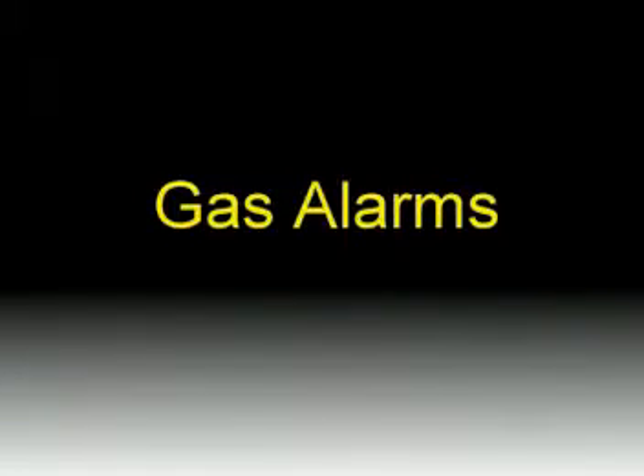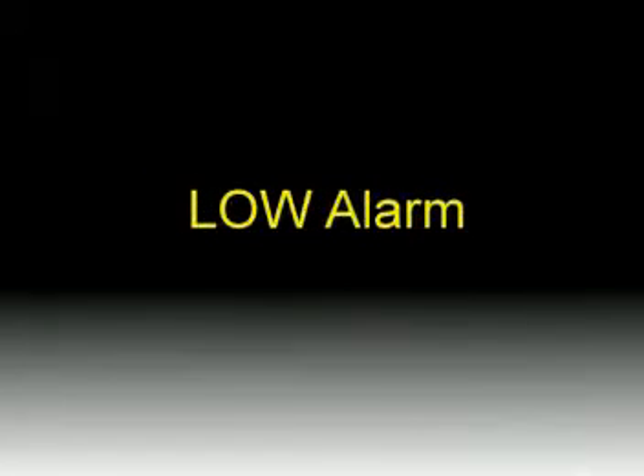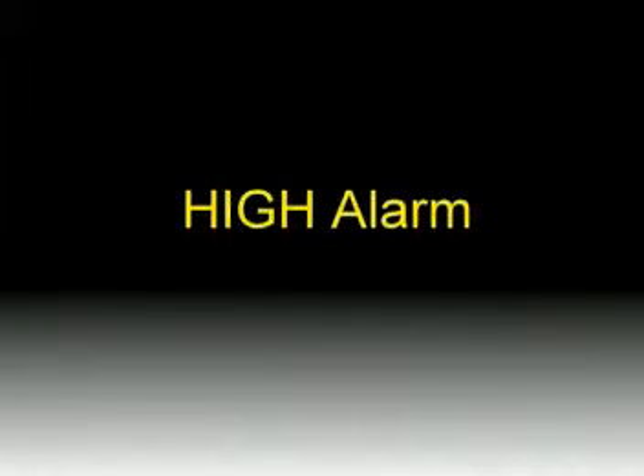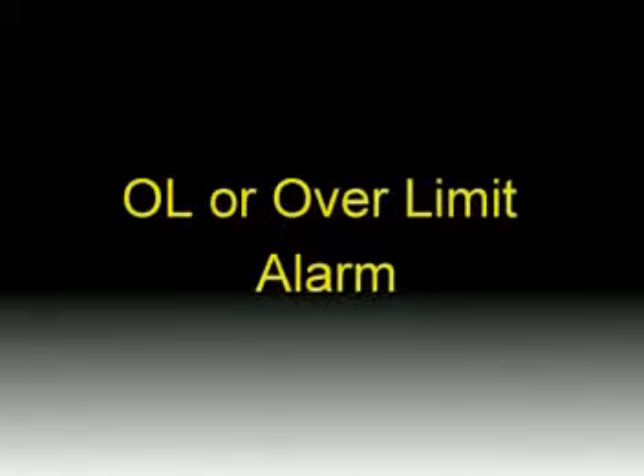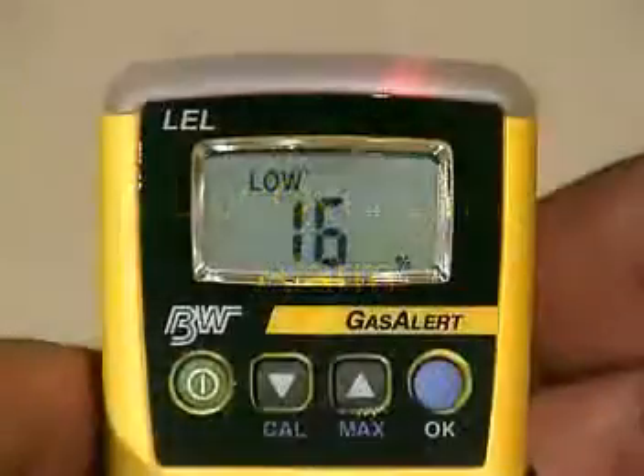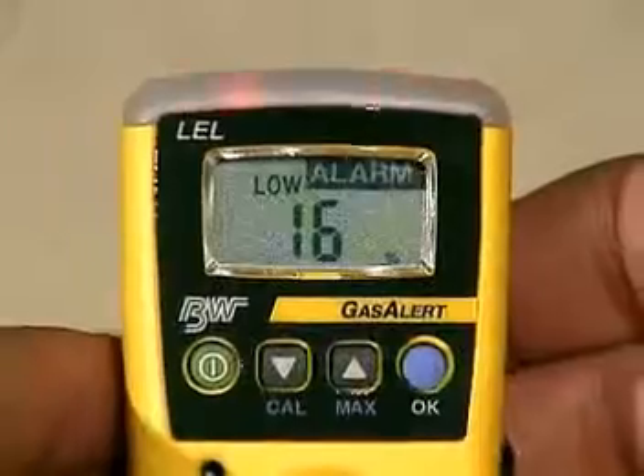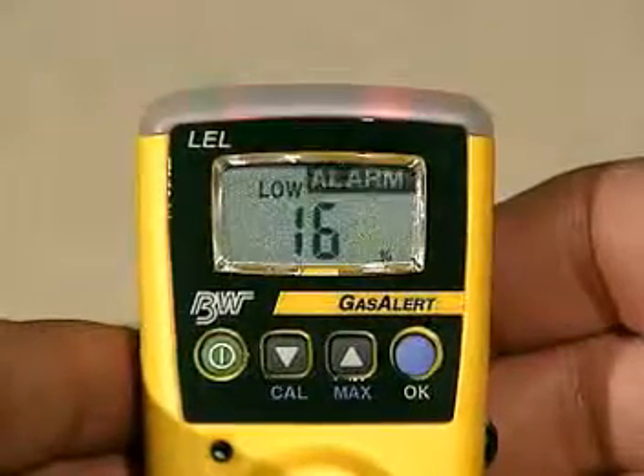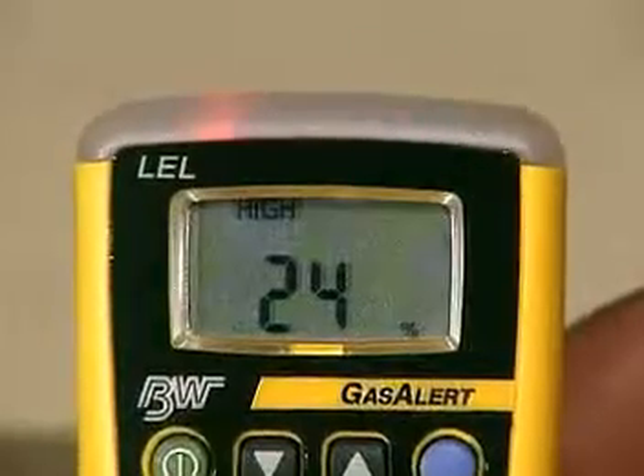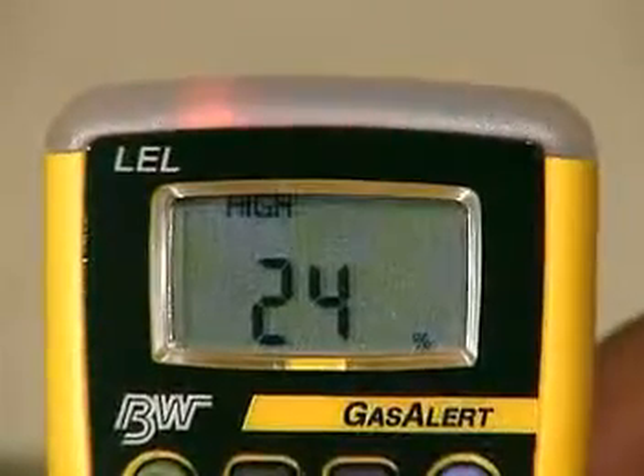The gas alarms activate when the preset levels are exceeded. The GasAlert-LEL clearly advises the level of danger encountered: instant low alarm, instant high alarm, and OL, or over limit alarm. In a low alarm condition, the audible visual alarms pulse slowly. In a high alarm condition, the audible visual alarms pulse rapidly in an urgent pattern.